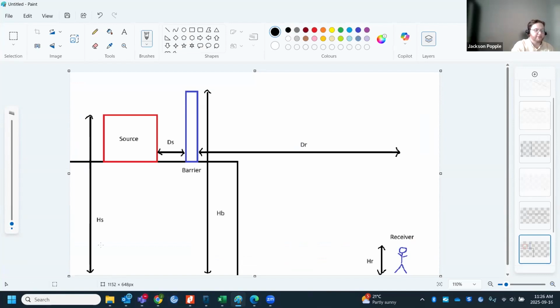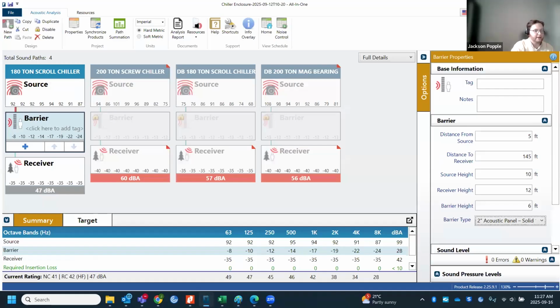If our building is, say, 20 feet tall, and we go back to our analysis, since our chiller is still 10 feet tall but the building is 20 feet, it becomes 30 feet total. The receiver height is still 6 feet, and the barrier height will be 32 feet—just knowing exactly what we're putting in there. In this case it doesn't change much because the path lengths are pretty similar.